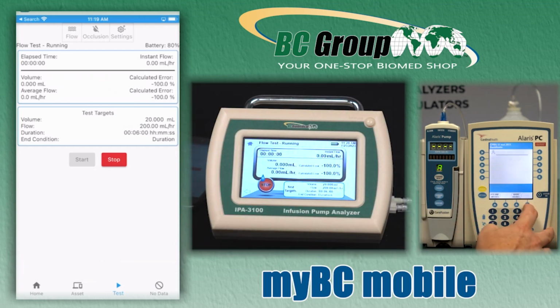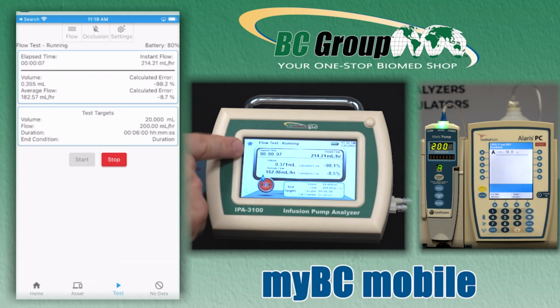We just hit start, and as soon as the pump starts, it detected the flow, started the timer, and now the test is running. So I don't have to worry about starting both at exactly the same time. If I were to do the manual start, then I would have to press start on the infusion pump at the same time as I press start on the IPA 3100 or the myBC mobile app.